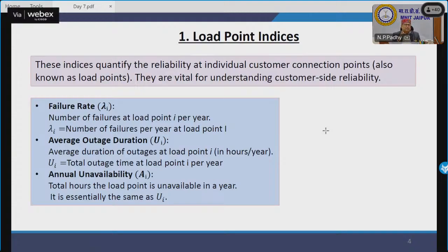So failure rate lambda is nothing but the number of failures per year at each load point I. What is average outage duration UI? It is the average duration of outages at load point I in hours per year. UI is the total outage time at load point I per year, meaning at a given year, how many hours, minutes or seconds I'm not getting electricity access.